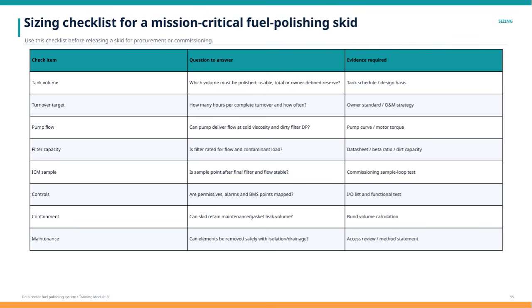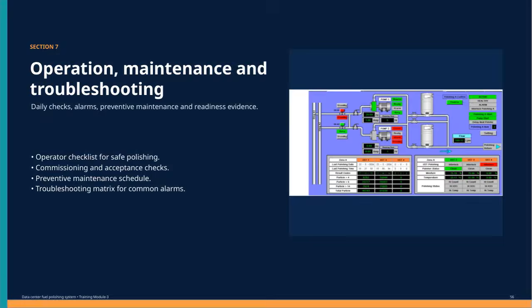Following this checklist helps guarantee that the fuel polishing system will operate reliably and meet both operational demands and safety standards. In this section, we'll focus on the operation, maintenance, and troubleshooting of the data center fuel polishing system. We'll cover daily checks and monitoring for alarms, which are crucial to ensure the system runs smoothly and safely. Preventive maintenance is another key area, helping us avoid unexpected failures by following a structured schedule. We'll also review the operator checklist designed for safe polishing practices, along with commissioning and acceptance checks to verify the system's readiness. Finally, we'll go through a troubleshooting matrix that addresses common alarms, enabling quick identification and resolution of issues. This comprehensive approach ensures the fuel polishing system remains reliable and effective.